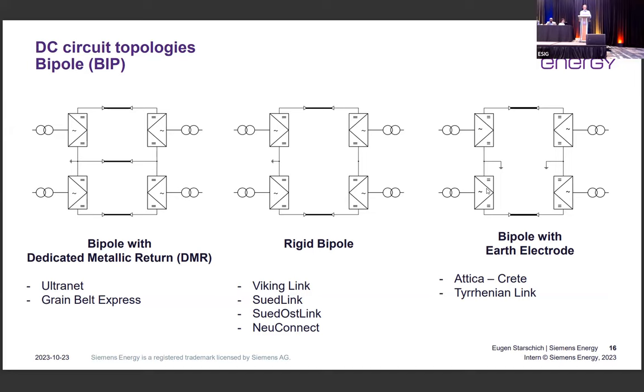In rigid bipole, we remove the dedicated metallic return and don't install an earth electrode, because it's probably not allowed. We are operating with four converters and two conductors. So of course you get some redundancy in terms of the converters, but you don't have any redundancy in terms of a DC cable. In case of a DC cable or DC line fault, you're losing the full transmission power. But nevertheless, this is probably one of the most popular configurations right now. The 2 gigawatt projects that have been presented by Johannes in Germany are using this rigid bipolar configuration.